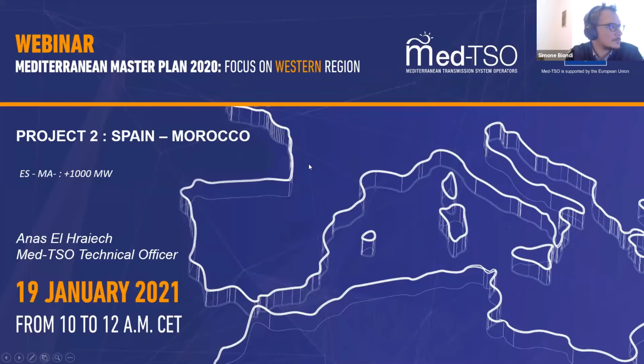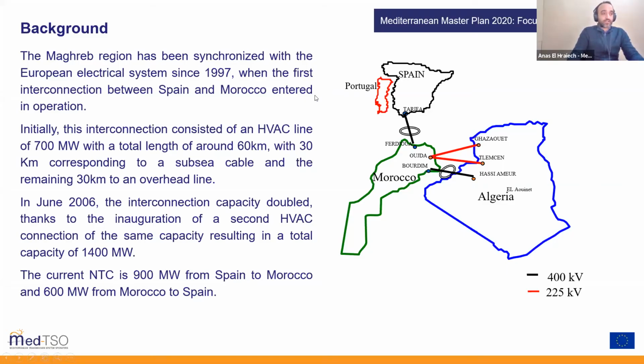For this project, things are a little different because we already have two interconnections between the two power systems at 400 kV. The total length is about 60 kilometers, 30 of which are submarine cable. It's AC technology, and the first link was inaugurated in 1997. This third project is a new link between the two continents and countries, offering an additional 700 megawatts of capacity. The current net transfer capacity is 900 megawatts from Spain to Morocco and 600 from Morocco to Spain.